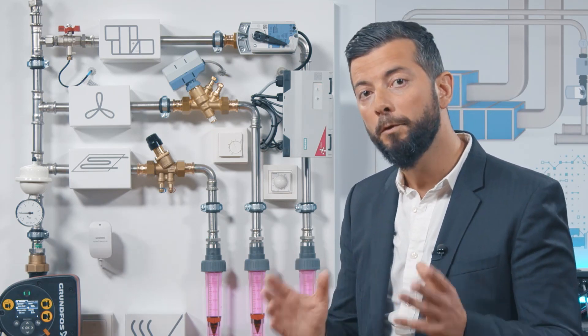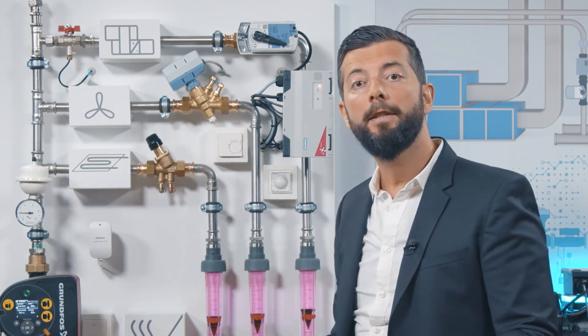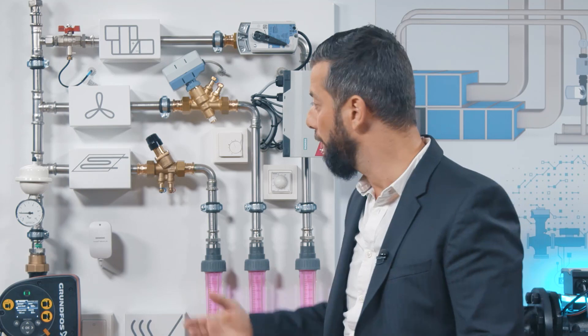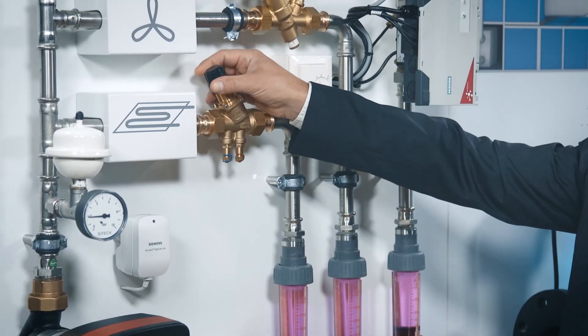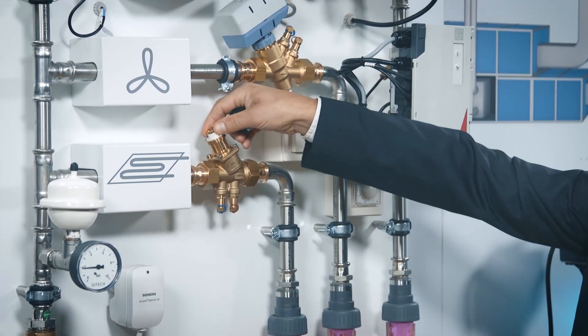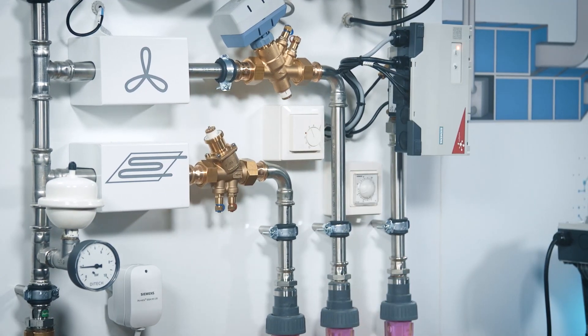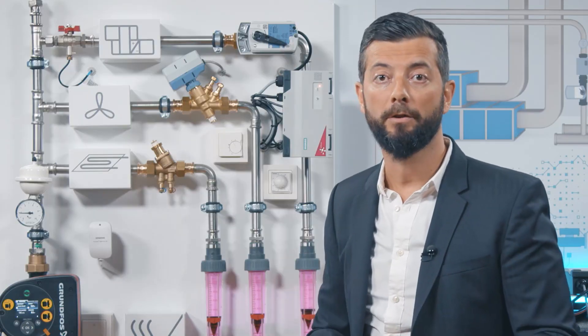And basically you have two ways to do that. For example, if you take our modulating PICV, first during commissioning you can adjust the maximum flow manually by touching this pre-setting. And as you can see now, I have established a new flow, which will also remain constant regardless of pressure fluctuations in the system.